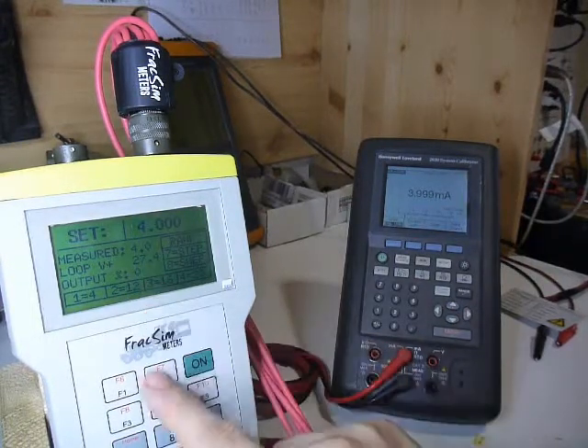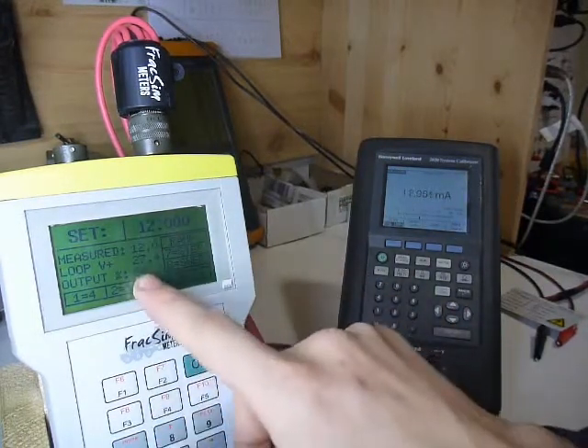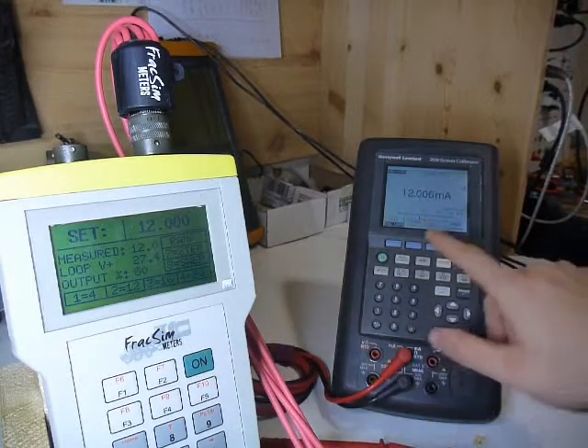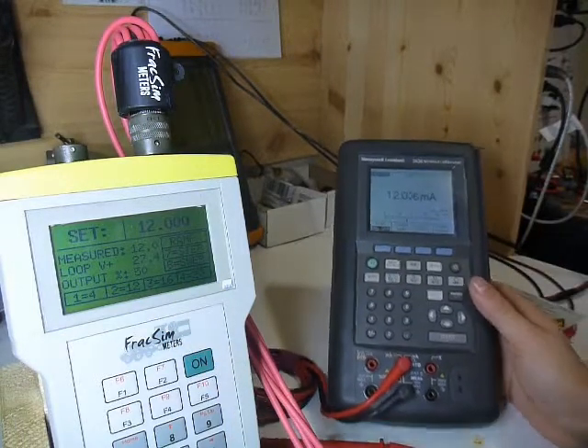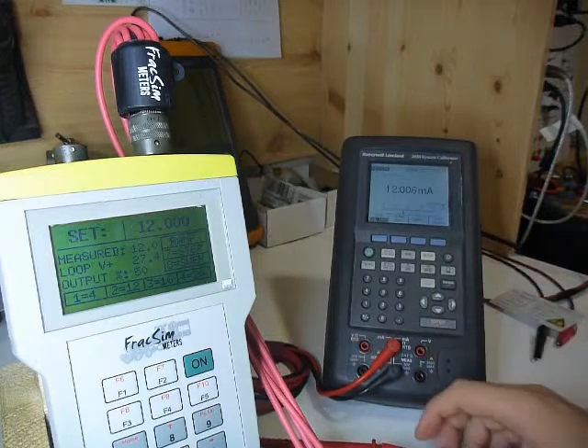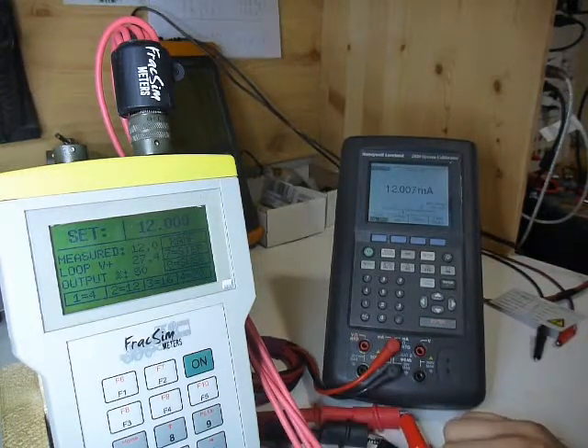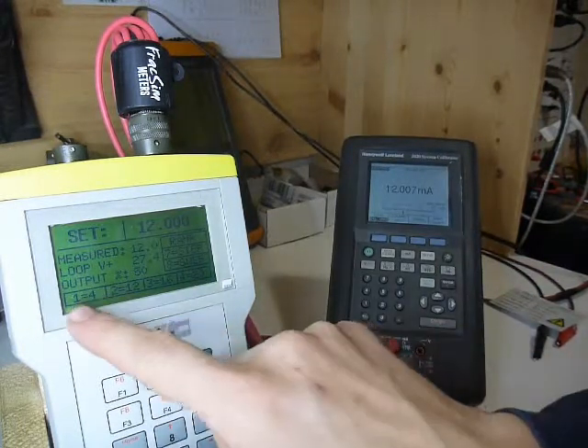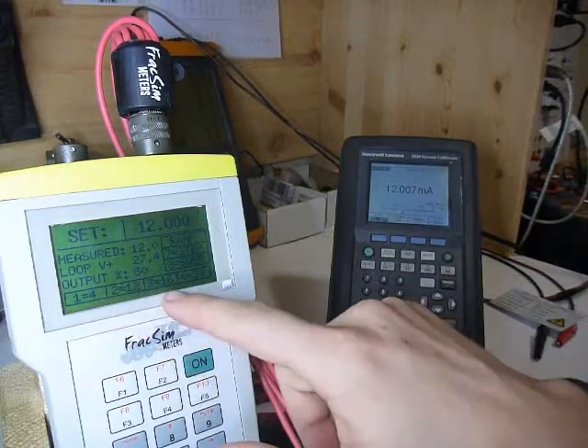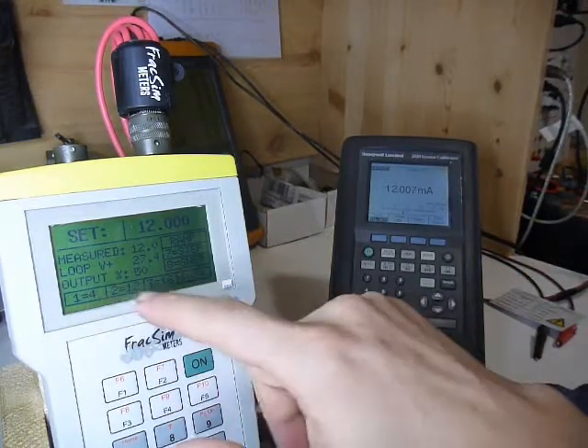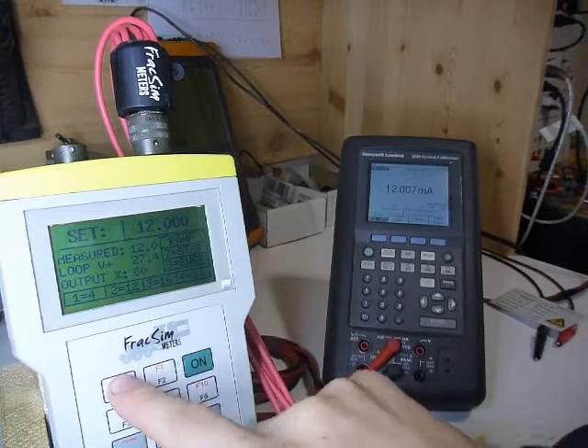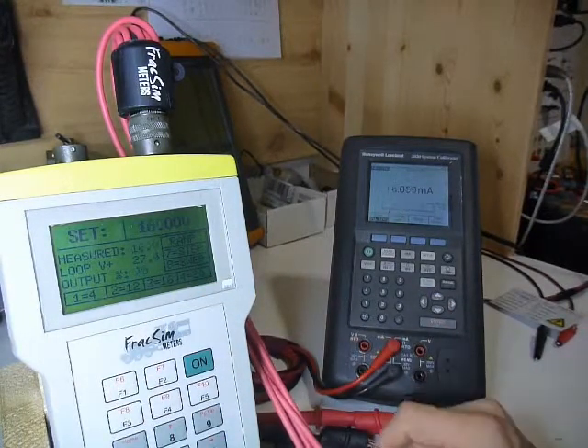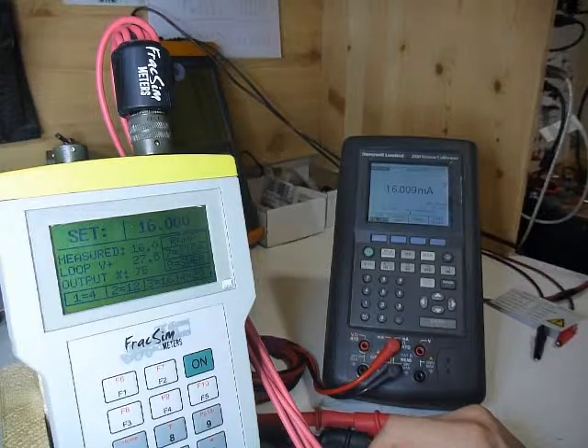So, for example, 12 milliamps, I'll just do 12 right now, would show 50%. You can see over here, this is just the actual reading, showing you over there what it's actually doing. Some other stuff you got on the screen here. So on the bottom you see 1, 2, 3, and 4, and the corresponding current value beside it. Those are just, if you just want 4 or 16 real quick, you can just press that.